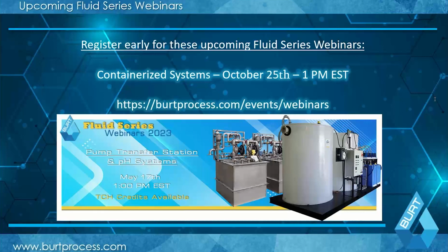About the biggest you can do in a single containerized system is about 200 gallons a minute. And that's because even though you have this large area, say 8 by 40, which if it was a skidded design, obviously is a very big system, when you're talking about a containerized system, you need to have all that access in that same area. So your actual sizing and your actual area in a containerized system is not that big, because you have all different walkways, access, and environmental controls built into your system. So you have a much smaller footprint than the true 8 by 40 feet in those cases.